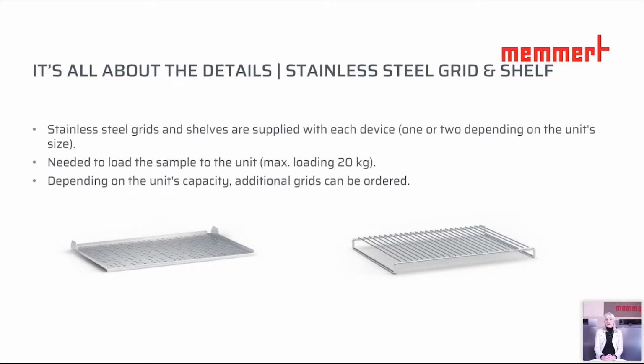Please, however, kindly take note that it also belongs to the position of the samples. So if you place in samples, please always leave a little bit of distance in between. Instead of the grids, we also have shelves. Shelves, which means this is in order to place in samples which are very small, where you need a very even surface, and which are also very stable. The picture here on the left side shows the perforated shelf for our CO2 incubators.